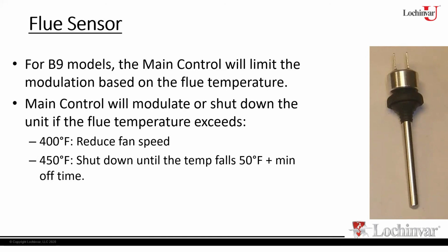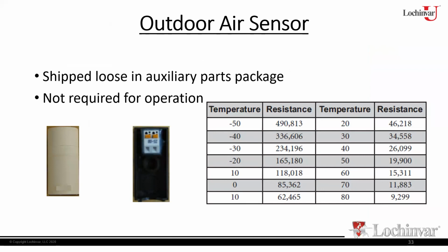All right. And then we have an outdoor air sensor. This would be only on boilers and it is shipped loose. It's your choice whether you wish to use it or not. I always recommend it in hydronic applications. For heating applications, you want to be able to see the outside air temperature and change your water temperature based on that. The standard sensor is, as you see it there, a 2-wire sensor. It's going to get wired back to the low voltage terminal board. You do have the option for what we would call the wireless outdoor air sensor. So basically you'd have a component that sits outside, then another component wired to the unit, but there are no wires between them. So that would be an option if you wanted to go that route. So you got a couple different choices there, but I always recommend using outdoor reset on hydronic systems because realistically you don't need 180 if it's 60 degrees outside in most cases. So you can lower that set point down.